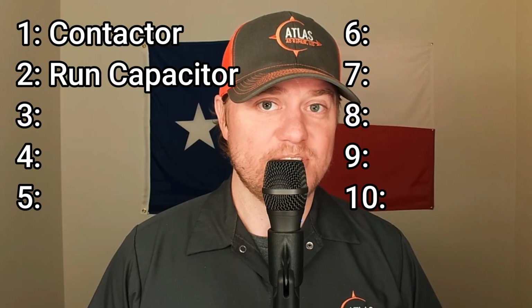And as a side note, there are some technicians out there that will intentionally overlook this item because changing out a contactor is fairly inexpensive versus having something like your compressor go out. Now you're dealing with a really big ticket. Now, a contactor does deal with high voltage, so if you're not used to dealing with electricity or working on an AC unit, I'd probably not mess with this component. And that's the same for our next component, which is the run capacitor.